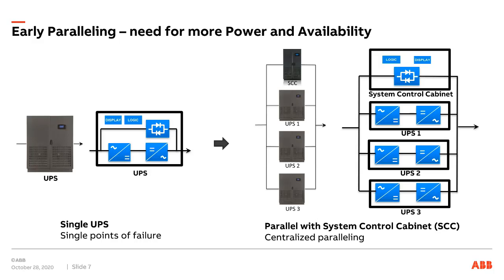It does offer filtering, it does offer backup, but if anything happens anywhere on that single power line between utility and the load, it's still not a good day. So to address that, the UPS industry came up with paralleling UPSs. Actually, the second reason for doing that is what has been true ever since: we need more power. The IT business, the data center business, seems to have an unlimited appetite for power. So a way of getting to that is by paralleling UPSs, and you parallel two UPSs, and now you double the power capacity.